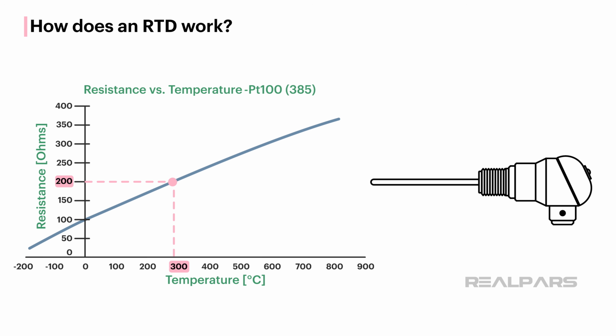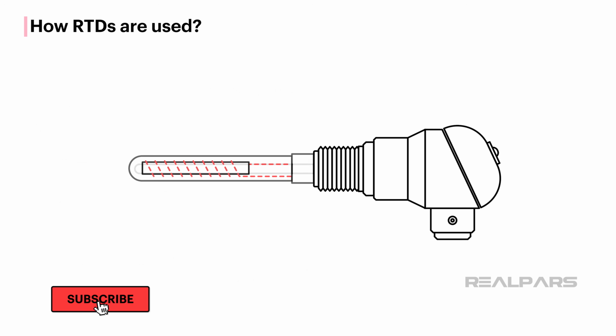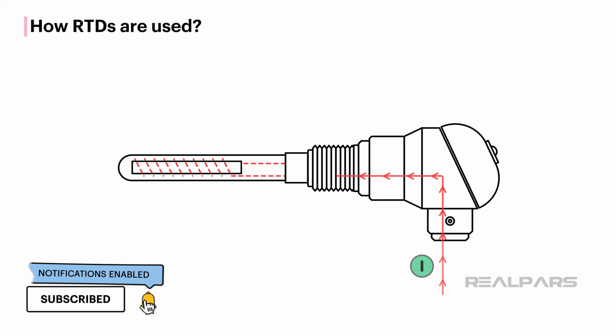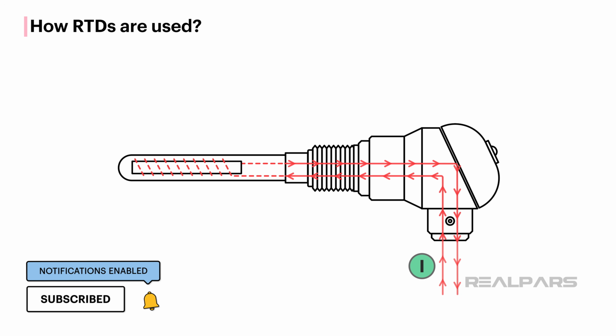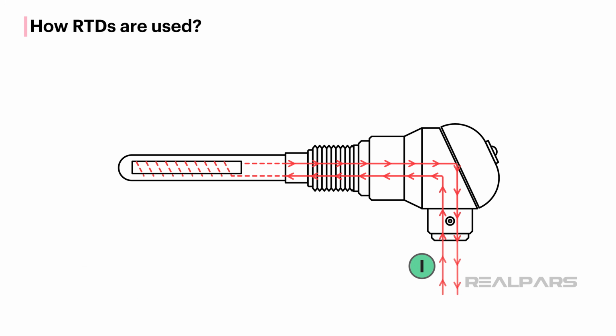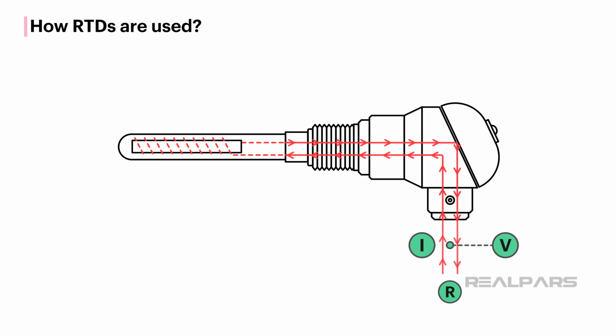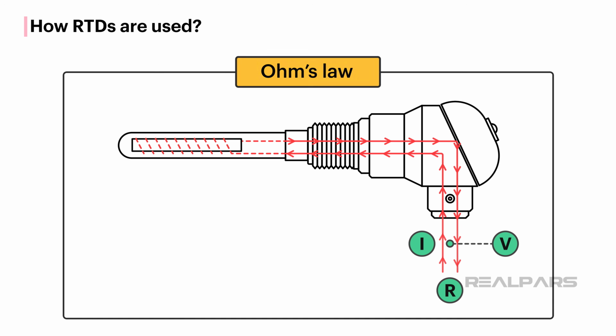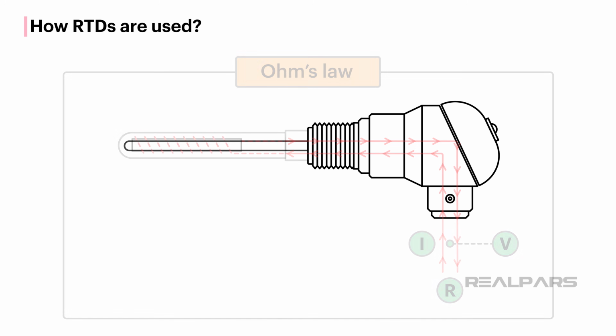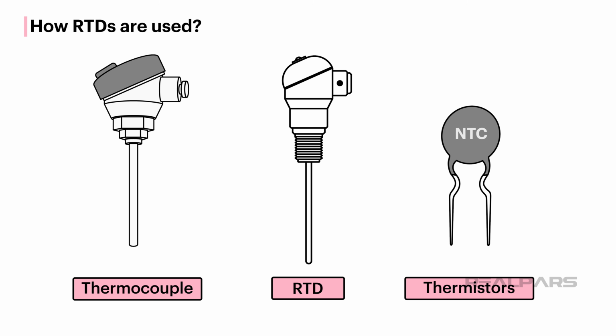That's not how it is done in industry. In most applications, a current is passed through an RTD to determine temperature. Using the resulting voltage across it, the RTD resistance can be determined using Ohm's law. We'll discuss how the voltage is created and how it is used to determine temperature later in this video. Other devices are used to measure temperatures, such as the thermocouple and the thermistor. What makes the RTD a good choice for a temperature measurement?